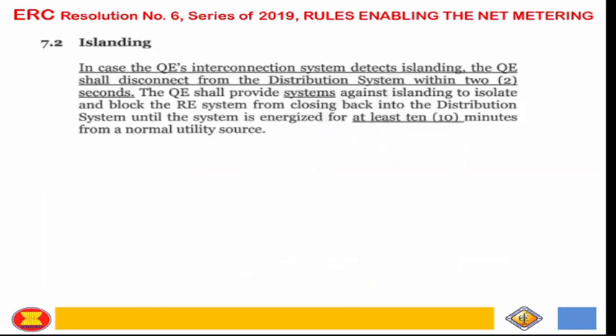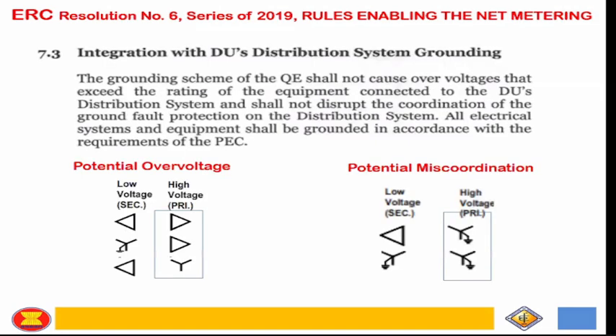And then islanding, it's interconnection device. Islanding QE shall disconnect from distribution within 2 seconds, no? Once na detect yung system is down, yung grid is down, at 2 seconds, ma-isolate ka. Okay? So yun yung any detection, no? Na islanding. And then the QE shall provide system against islanding to isolate and block the RE, no? May blocking din, no? At least 10 minutes bago ka magsisynchronize na naman sa grid. So that's the provision or requirement, no? Yun yung kailangan i-comply natin with the time, no, na requirement because if not, magkakaproblema talaga, no, yung coordination between the utility and then the DG because of those potential risks.